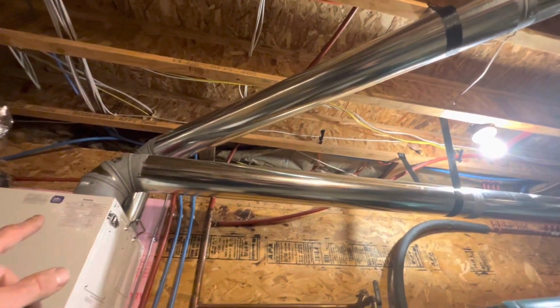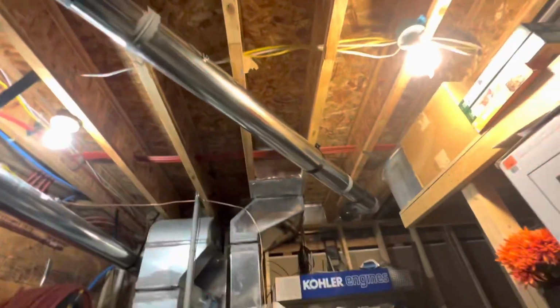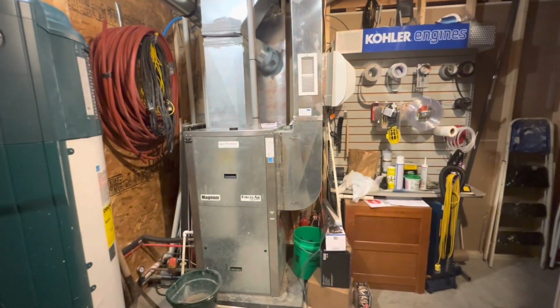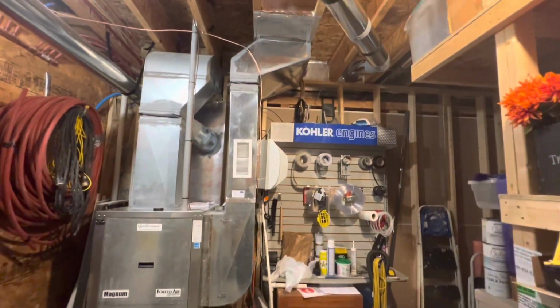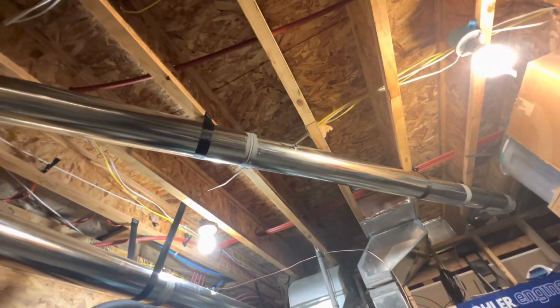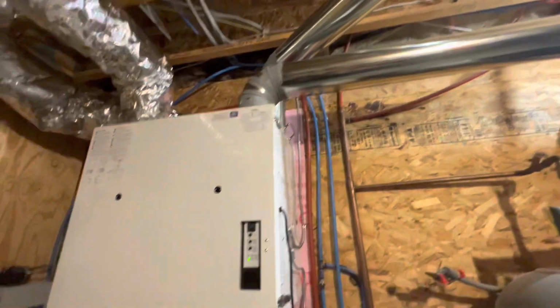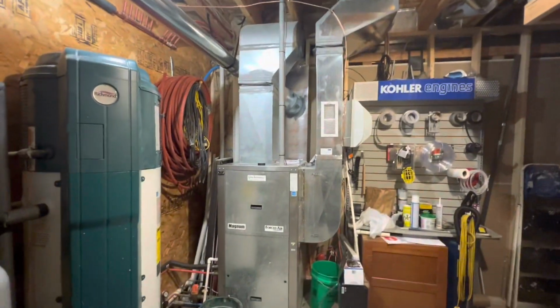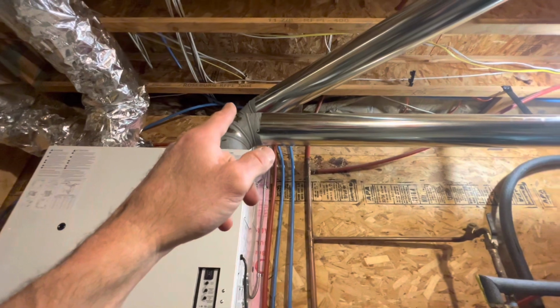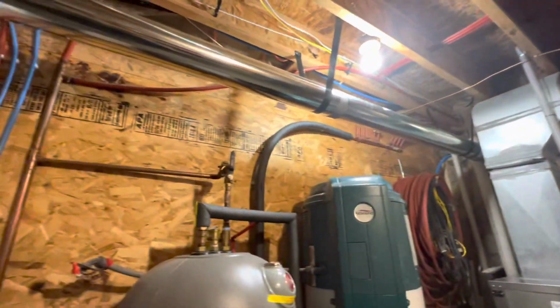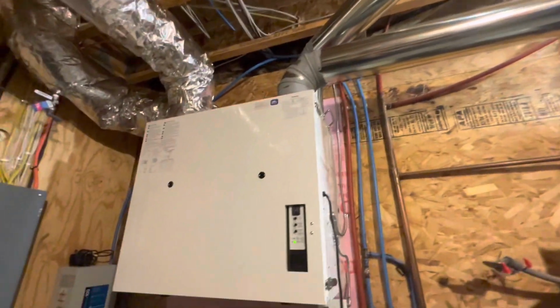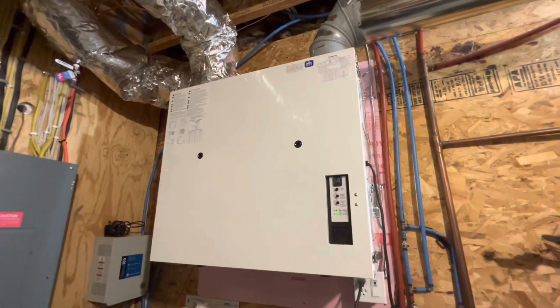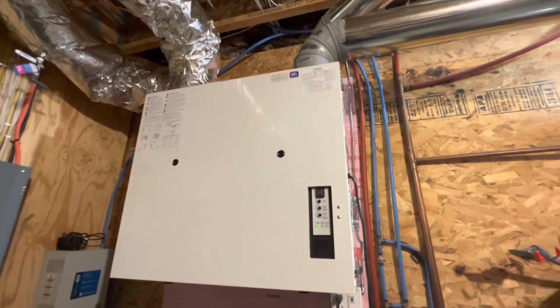The reason is that since this is dumping back into my HVAC return, the supply fan for the HVAC is also sucking air at the same time. So they have you put that damper in there so you can make sure that the fans in the ERV are supplying the right amount of air with the influence of the HVAC fan. If I would have elected to install the supply dump line into a different spot in the house, not associated with the HVAC, I wouldn't have needed that, and essentially there isn't any calibration. They just are what they're set at. But since I did that, I need to calibrate that.